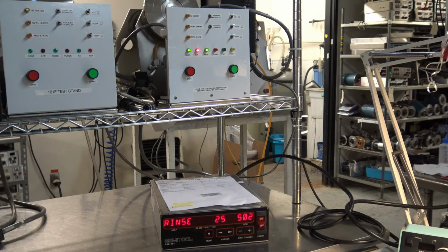So I spoke about our SRD spare parts and service. We also do full system refurbishments. We recommend our customers refurbish their SRDs every 5 to 10 years, depending on the amount of usage the tool is getting. When we refurbish an SRD, we break it down to the component level, clean and test all parts for full function, and replace all parts as necessary. When we send back a refurbished SRD to a customer, it comes in like new condition.